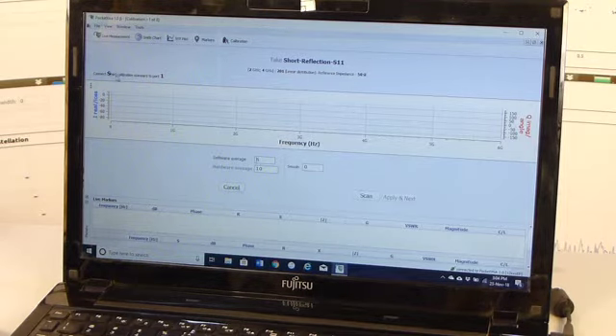Now it says connect short calibration standard to port 1. Now this is a short, I will connect this to port 1. You have to be a little gentle while tightening these ports. Now we will press scan. Now when we press scan, it will start doing the scanning, as you can see, because the average is 5, so it is taking a little time.